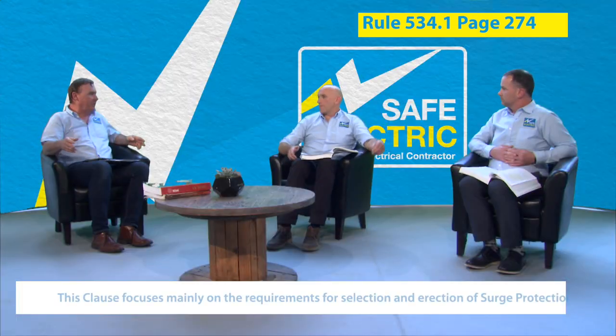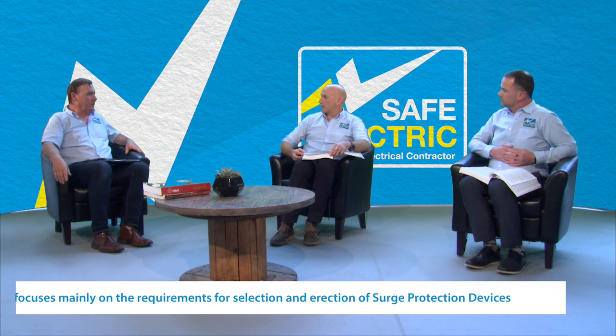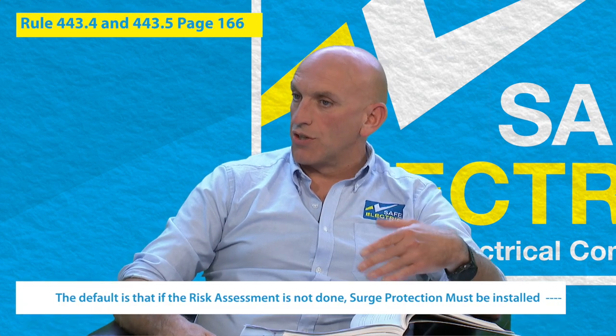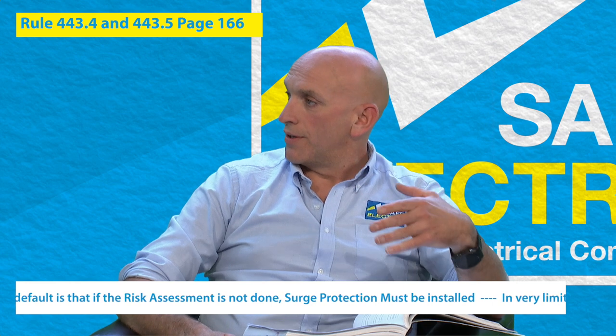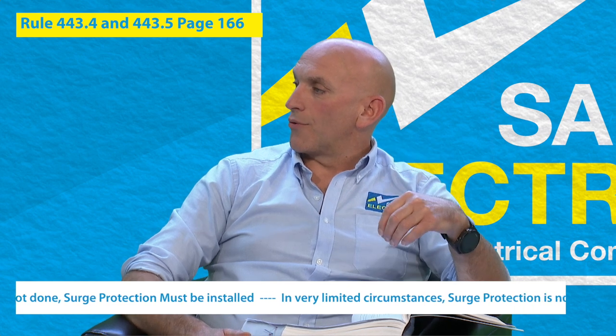And the new rules also deal with surge protection, which I don't think was even hardly mentioned in the old rules. So could you, John, fill us in on that? Yeah, very similar to the arc fault detection, we're recommending this to a client. Surge protection in the fourth edition was a recommendation that we should have always been making to our clients, especially now with the amount of electronics that have been introduced into domestic, commercial, and industrial settings. So, slight change now with the IS 10101: if we are not introducing surge protection, we now have to carry out a risk assessment.